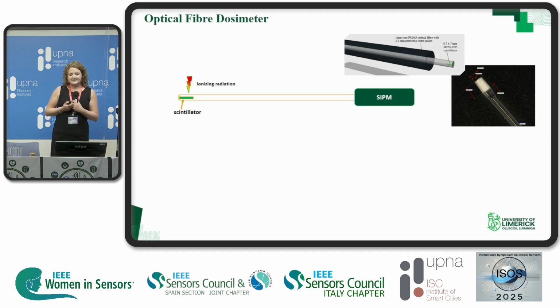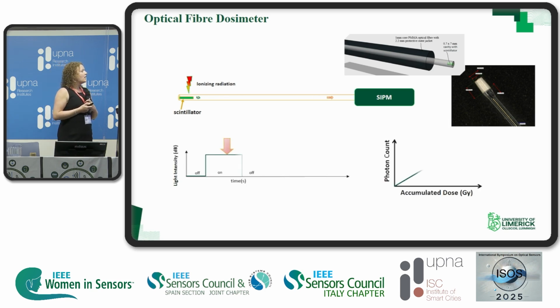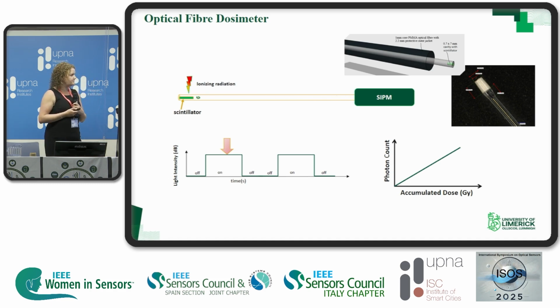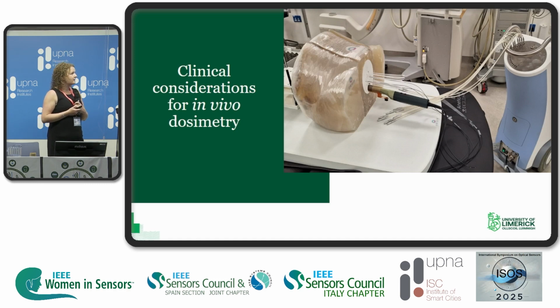Our sensors are based on radioluminescence, where we have a scintillating material at the tip of the fiber. This can be either embedded into the core of the fiber or attached as an additional tip. When it's exposed to ionizing radiation, it gives off light which travels through the optical fiber to the photodetector, and then we monitor that light signal over time to give us the accumulated dose being delivered to the patient.